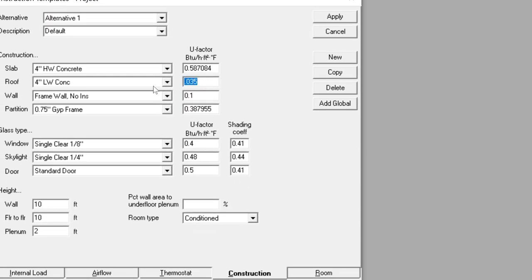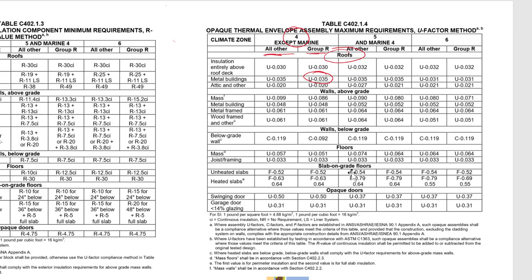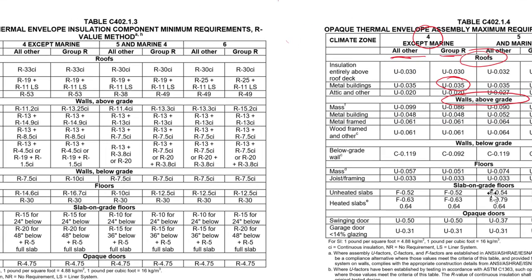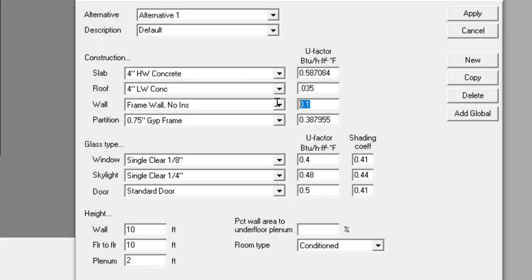So we'll set the roof at U = 0.035. For the wall above grade, we go back and look for the highest U-value across the two columns. The highest value is 0.099, and we're going to round that up to 0.1, so we'll put in 0.1 for the wall.